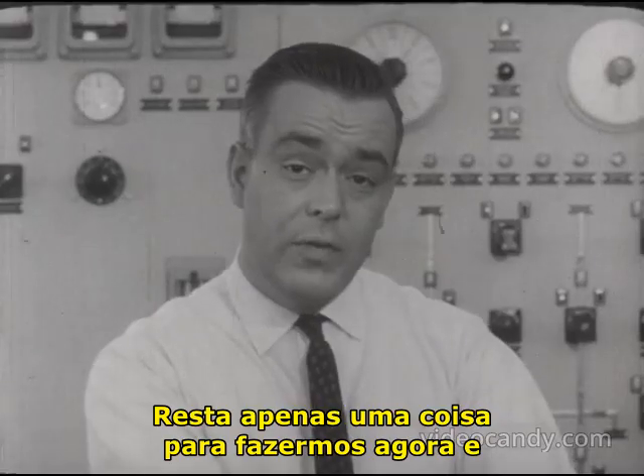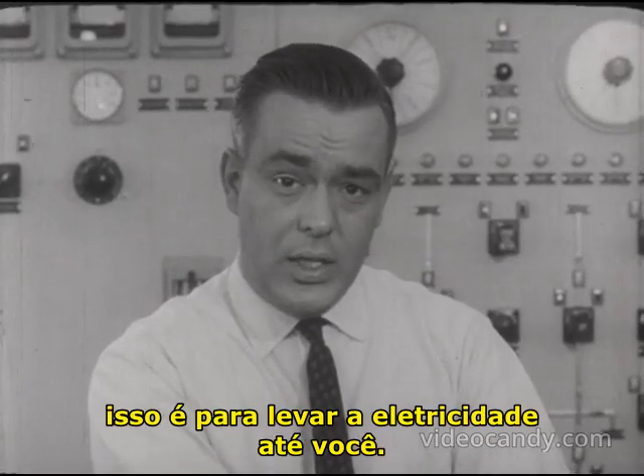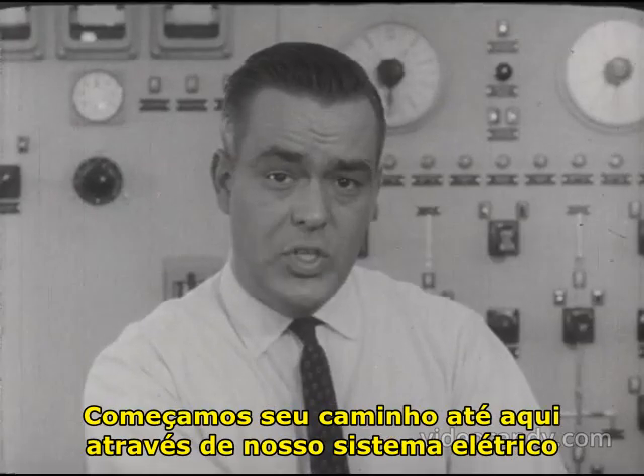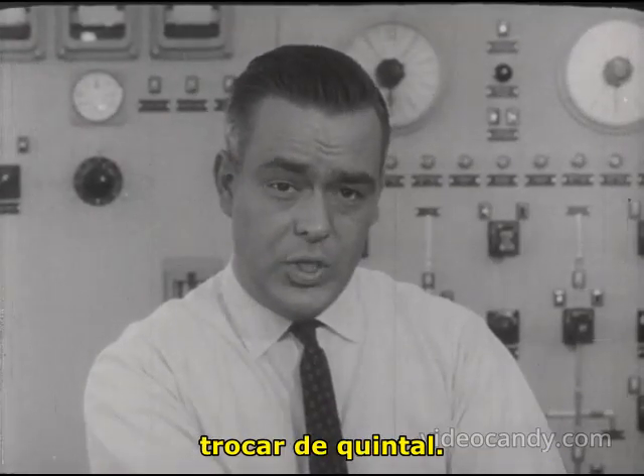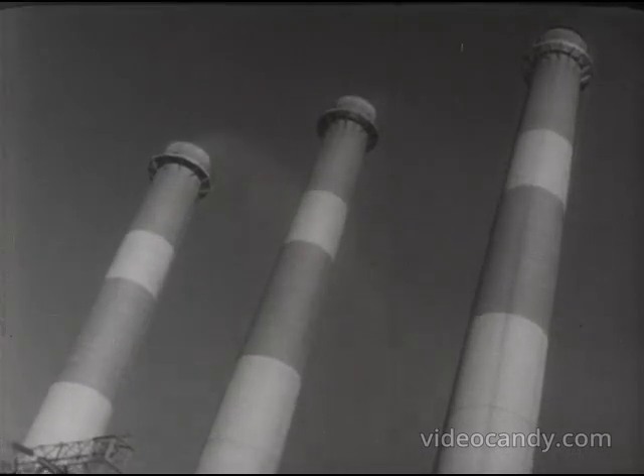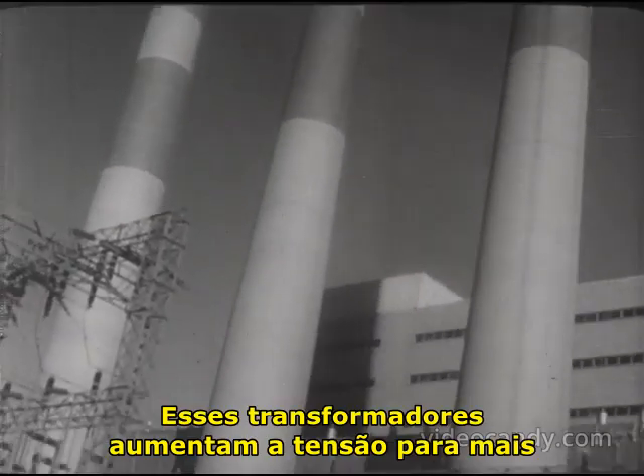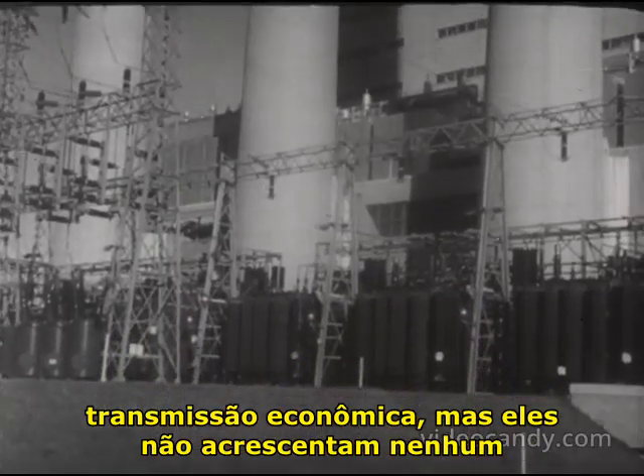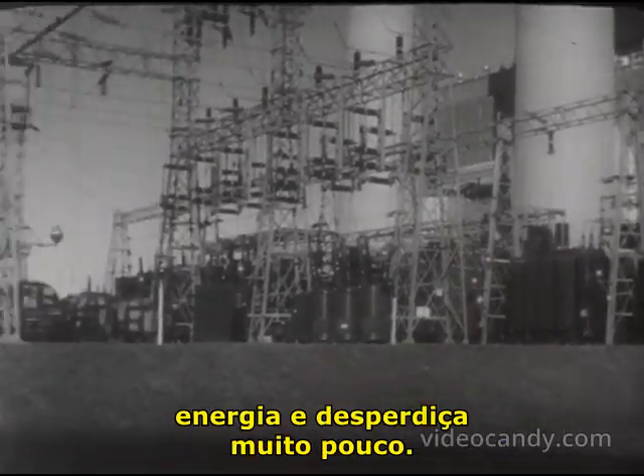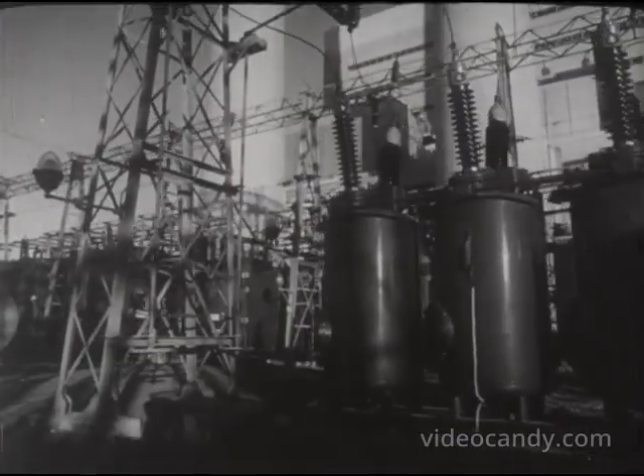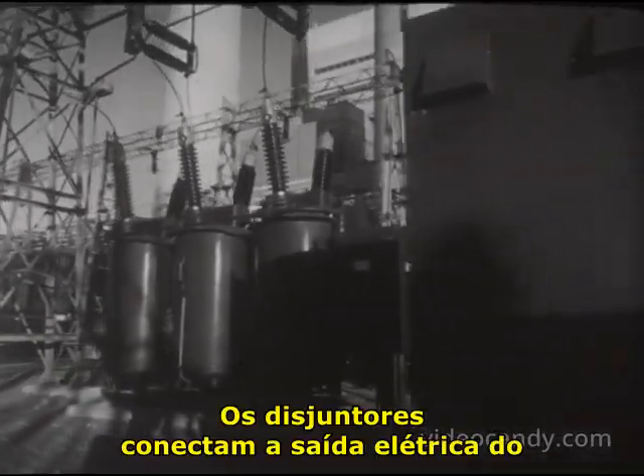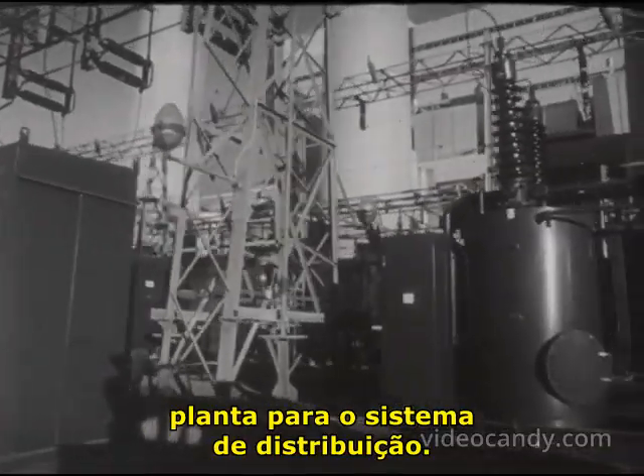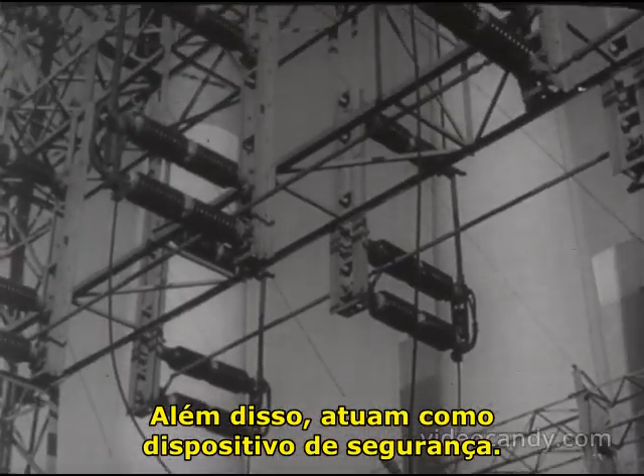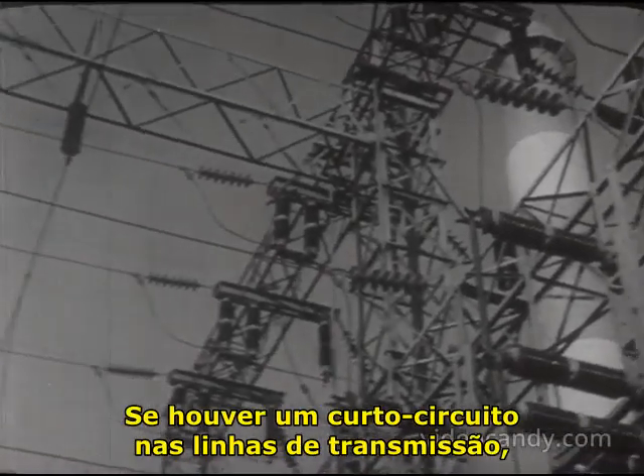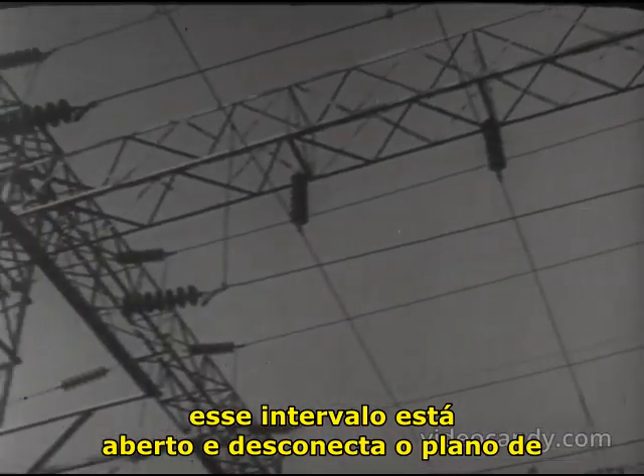There remains just one thing for us to do now, and that is to get the electricity to you. We start it on its way here through our electrical switch yards. These transformers step up the voltage for more economical transmission, but they don't add any energy and waste very little. Circuit breakers connect the electrical output of the plant to the distribution system. In addition, they act as a safety device. If there is a short circuit on the transmission lines, these breakers open and disconnect the plant from the line.